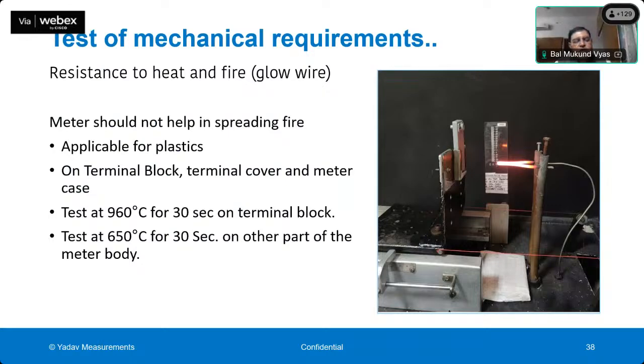So the temperature limit specified is 960 degrees centigrade for 30 seconds. The terminal block plastic is subjected to this temperature, 960 degrees centigrade, which you can see on the right hand side in the picture. The red hot iron element is applied to the terminal block, and it is seen that if the terminal block catches fire, then within how much time it self-extinguishes. It should not take more than 30 seconds to extinguish the flame.